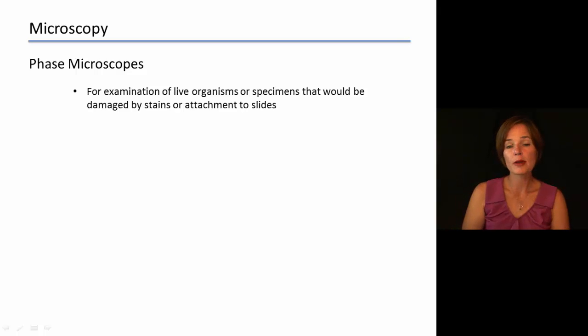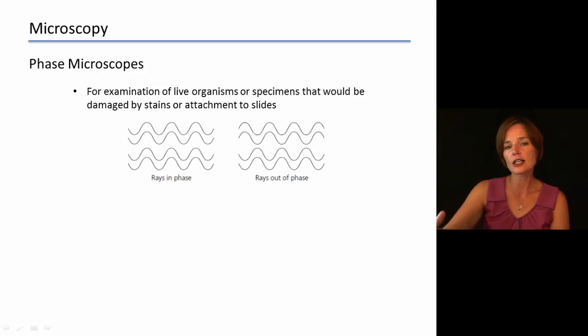Phase microscopes are really good for examination of live specimens, and also for studying specimens that would be damaged by the use of stain or by attachment to slides. Ultimately, what the phase microscope does is alter the phase, or the syncing, of the rays that are passing through the specimen and through the lenses. This is used to enhance the contrast of the sample, and since it increases the contrast, we can get away with not using stains.